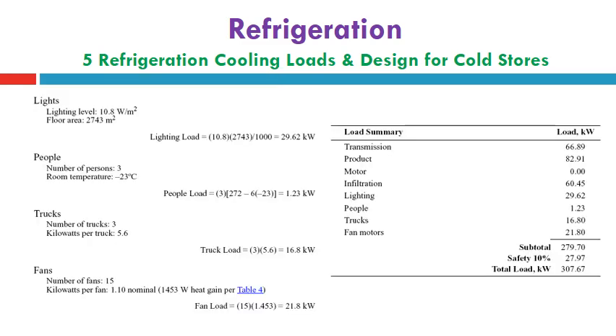The internal loads are finally to be estimated. For lights, you take a lighting level of 10.8 watt per square meter according to the floor area of 2743 meter square. He can estimate the total lighting load by multiplying and dividing finally over 1000 to get it in kilowatt. He found that the lighting load is 29.62 kilowatt. For the people load, he assumed 3 persons, and the room temperature is -23. He gets the required difference by the equation listed before for people load, and the total people load is 1.23 kilowatt. Trucks, he assumed 3 trucks, 5.6 kilowatt per truck. So the total of these forklift trucks inside this refrigerated space is 16.8 kilowatt.